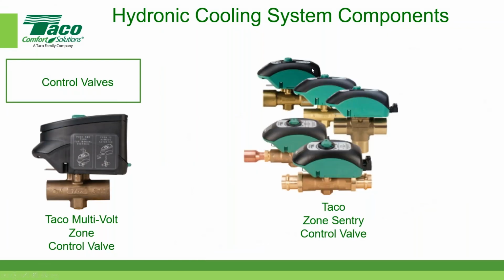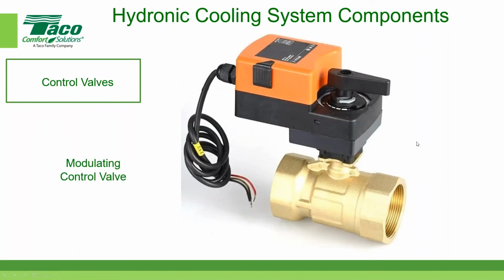We're almost there. Control valves. You can use Taco manufacturer's Zone Sentry valve, which can be used for hydronic cooling systems. And we also have a multi-volt zone control valve. These are typically used on fan coils for relatively small flows. For larger flows, you would use a third party.